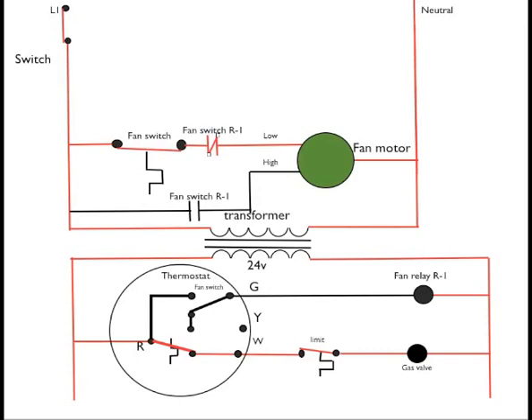Okay, let's sequence this thing in the low voltage first. Power passes through R, through the now closed heating thermostat, through W to the normally closed limit to energize the gas valve. Power passes through the fan switch. When the heat exchanger warms, it'll close. Power passes through the normally closed fan switch R1 to energize the fan in low speed.